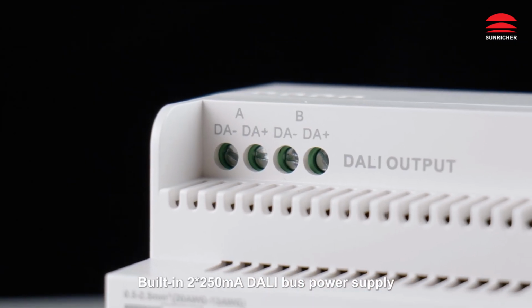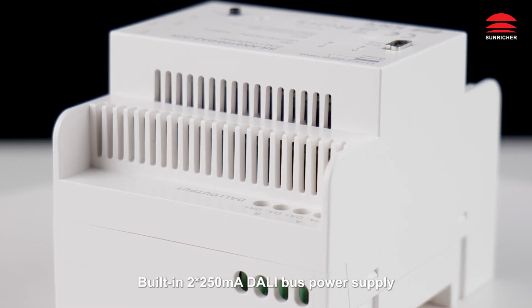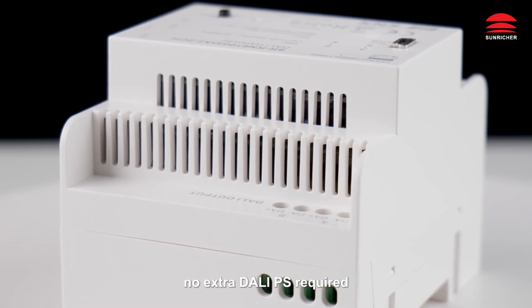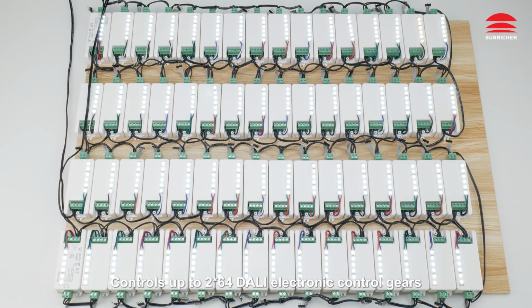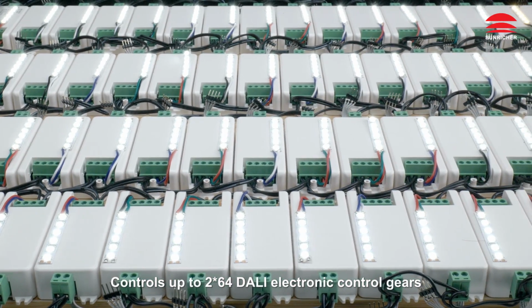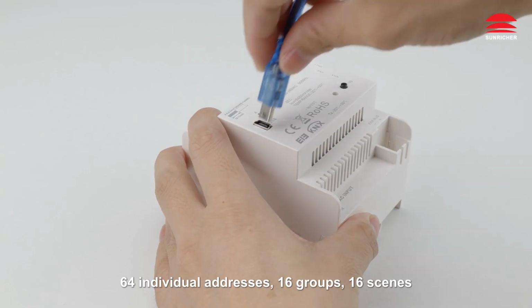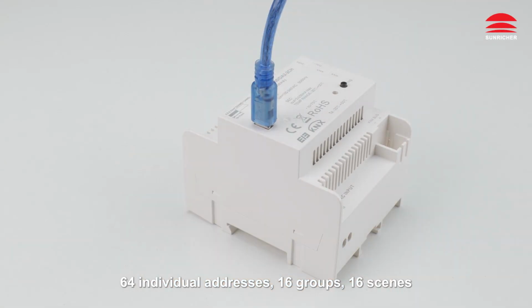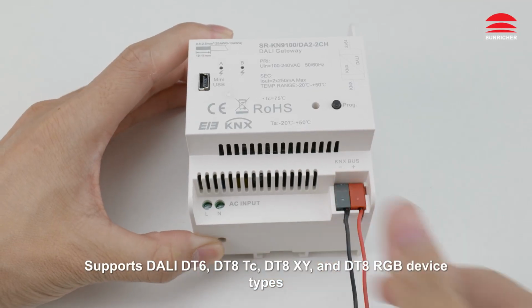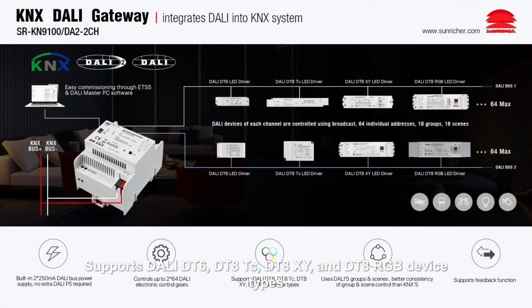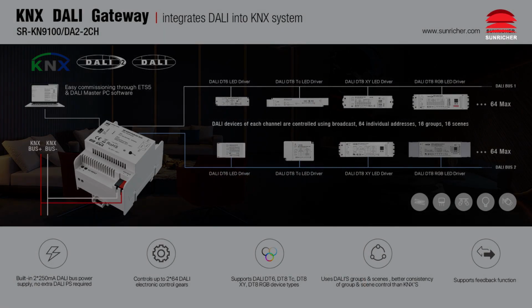Built in 2*250mA DALI bus power supply, no extra DALI power supply required. Controls up to 2*64 DALI electronic control gears. 64 individual addresses, 16 groups, 16 scenes. Supports DALI DT6, DT8TC, DT8XY, and DT8RGB device types.